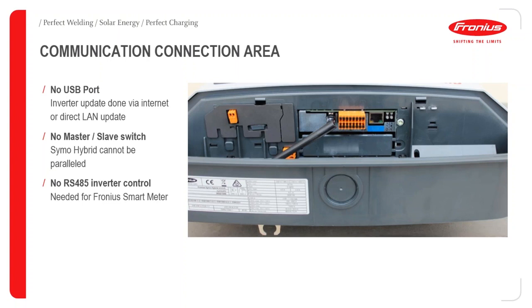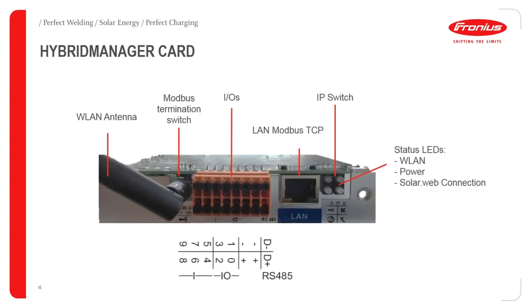So the meter and the battery, if they're in the system, they're in there as slaves. So that's why you don't have the master-slave switch. And the one thing to remember as well is, if you're looking at using external controllers to control the inverter, you can't control the inverter via RS485 as you can with the other ones, because we use that port for the meter. So if you did want to externally control the inverter, then you can do that via Modbus TCP, which is done via the LAN port if needed.